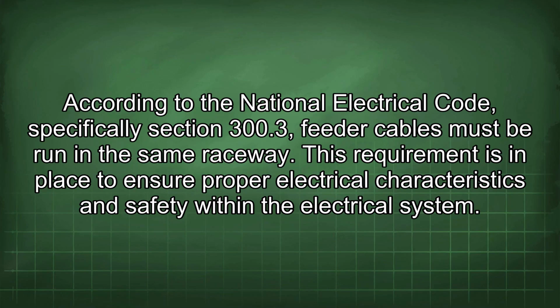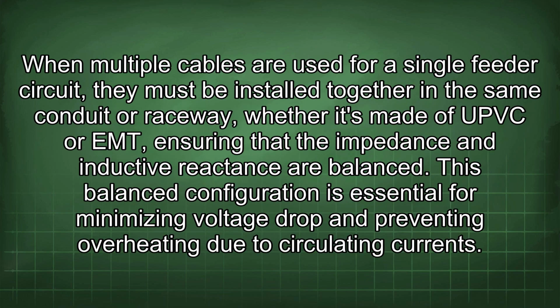According to the National Electrical Code, specifically Section 300.3, feeder cables must be run in the same raceway. This requirement is in place to ensure proper electrical characteristics and safety within the electrical system. When multiple cables are used for a single feeder circuit, they must be installed together in the same conduit or raceway, whether it's made of PVC or ENT, ensuring that the impedance and inductive reactance are balanced. This balanced configuration is essential for minimizing voltage drop and preventing overheating due to circulating currents.